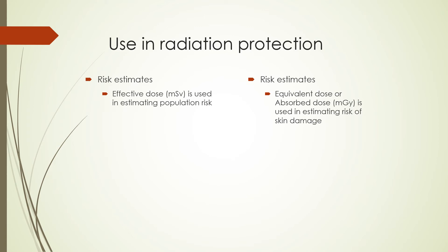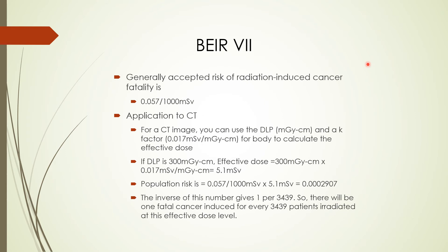Effective dose is used in estimating population risk. Population risk refers to the induction of additional cancers in the population as well as hereditary effects. In diagnostic imaging, equivalent dose or absorbed dose is used in estimating deterministic effects like skin damage from interventional radiology procedures. Risk estimates are based on the Biological Effects of Ionizing Radiation Committee's report, known as BEIR VII. BEIR VII is based on data collected from survivors of atomic bombs dropped on Hiroshima and Nagasaki, survivors of radiation accidents, people irradiated for medical reasons, radium dial painters from the early 20th century, and other radiation-related events. Based on the BEIR VII report, the generally accepted risk of radiation-induced effect is 0.057 per sievert.